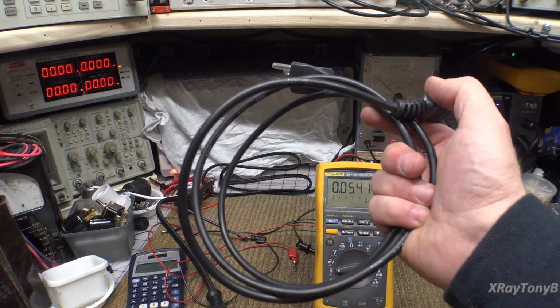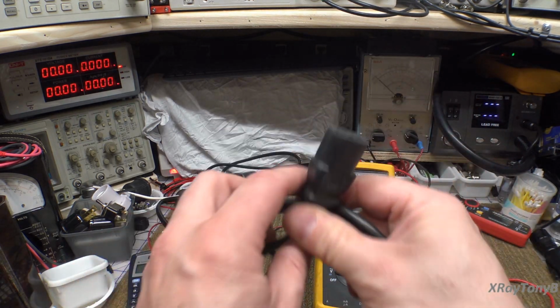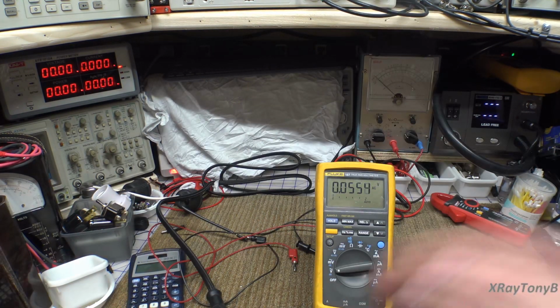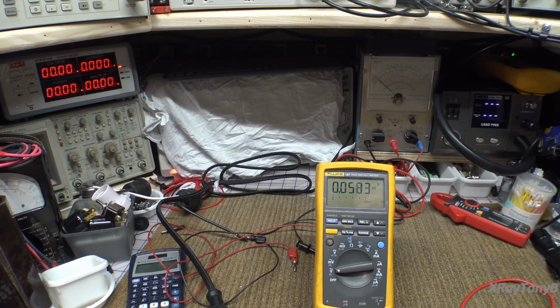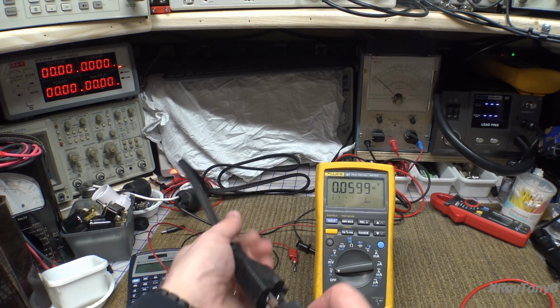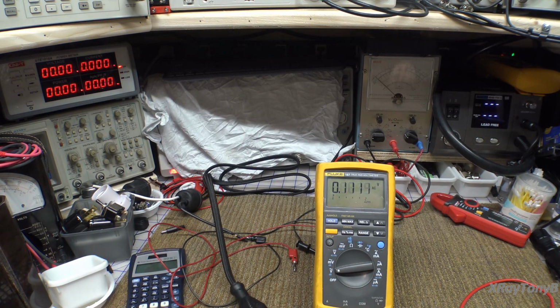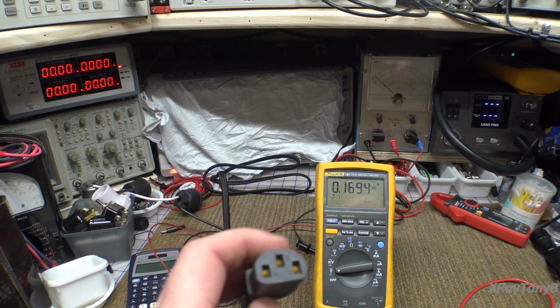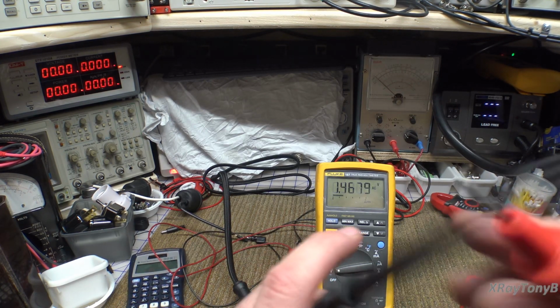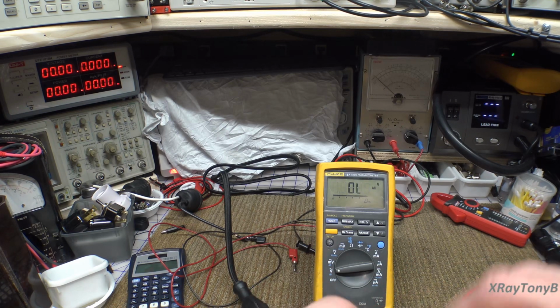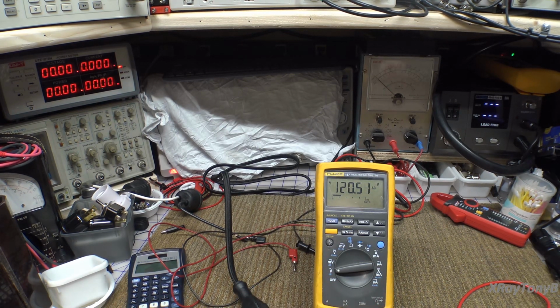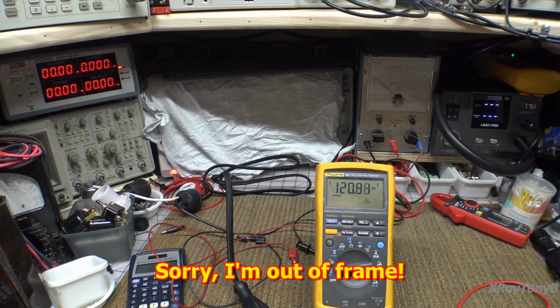All right, so here's a standard power cord, and I'm sure you've seen these many times. If I plug it into a standard outlet, it should come as no surprise that if I measure from the neutral to the line, I get my 120 volts. But what some of you may not realize is if I measure from earth to line, I still get 120 volts.